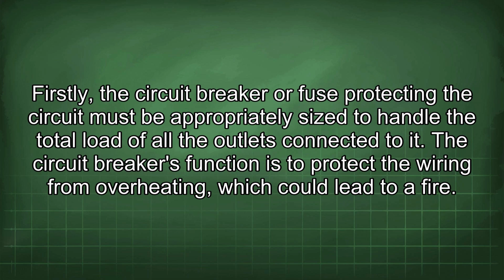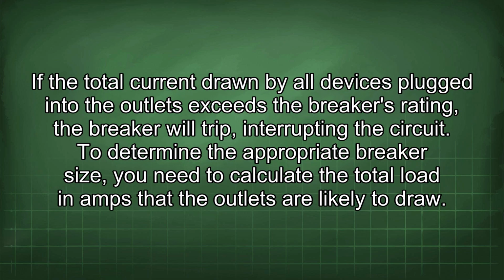Firstly, the circuit breaker or fuse protecting the circuit must be appropriately sized to handle the total load of all the outlets connected to it. The circuit breaker's function is to protect the wiring from overheating, which could lead to a fire. If the total current drawn by all devices plugged into the outlets exceeds the breaker's rating, the breaker will trip, interrupting the circuit. To determine the appropriate breaker size, you need to calculate the total load in amps that the outlets are likely to draw.